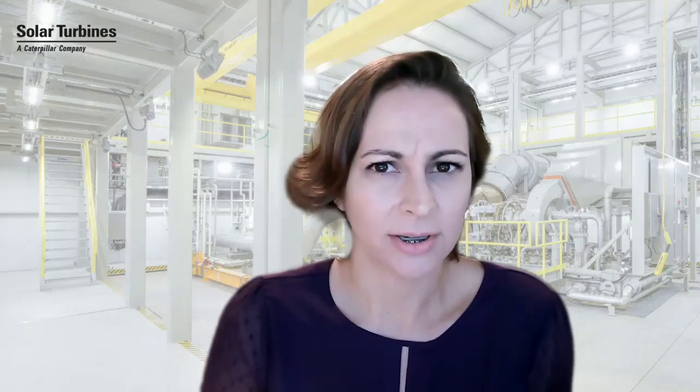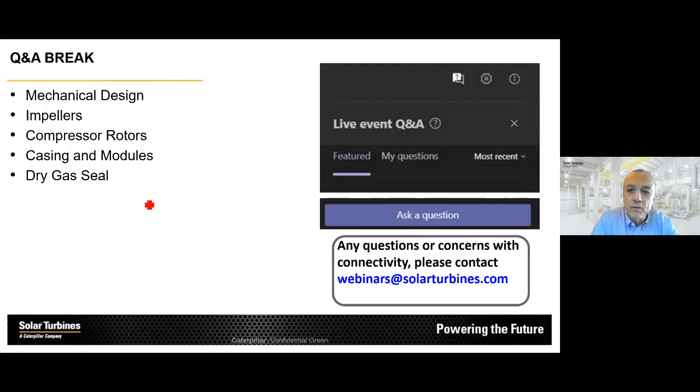I see. So it's an ease of maintenance type of approach. This kind of goes into another question, I think, that we have here: can you remove that bundle in one piece then? Is it ease of access and easy to restage? Yes, the bundle can be removed in one piece, and then you can either assemble and disassemble at site, although we normally recommend going into a repair shop, mainly because you want to have clean and dry conditions when you assemble and disassemble these components. Great. Sounds like a really flexible design then.